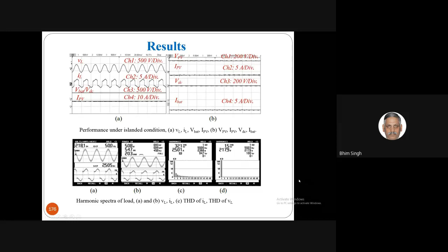But when the grid appears, after around 3 to 4 cycles, it synchronizes to the grid and the grid is closed. But the load does not experience when the grid disappears and appears. So you can think about how smoothly the synchronization happens as grid currents start appearing here. And of course, it takes a synchronization algorithm, because we have to bring the angle of the converter inverter system closer to the grid, and once it comes close, then we close the system. So smooth transition is also very important in this case.